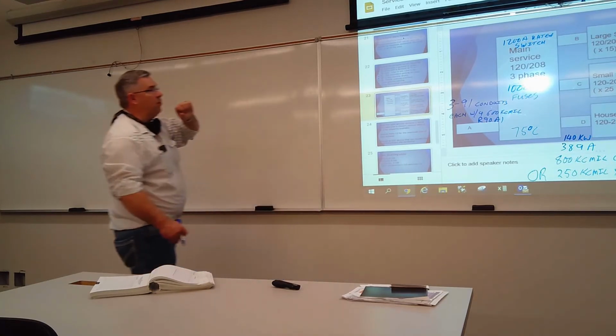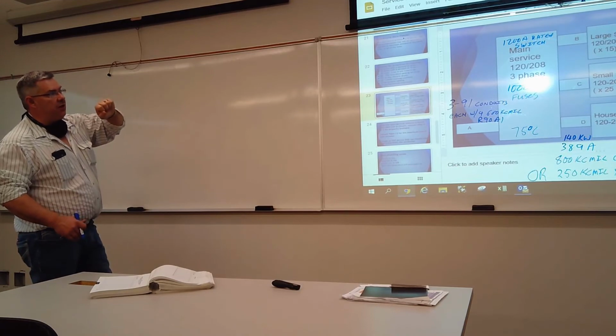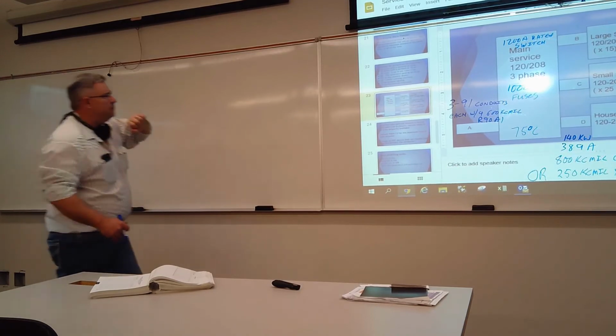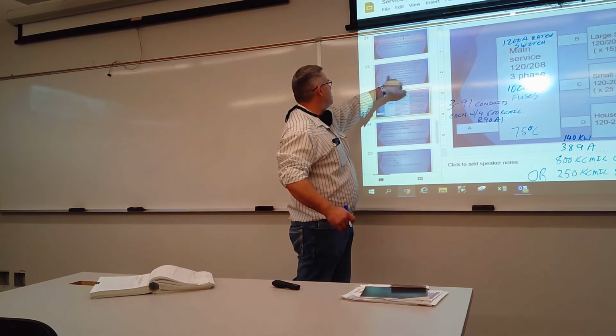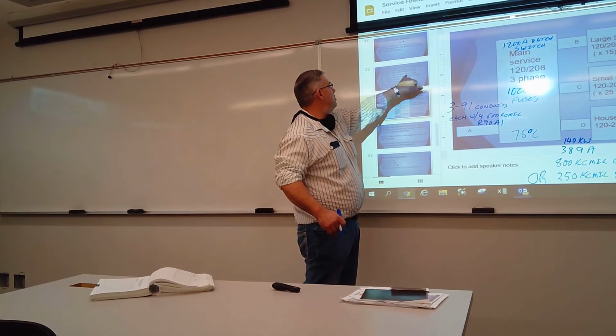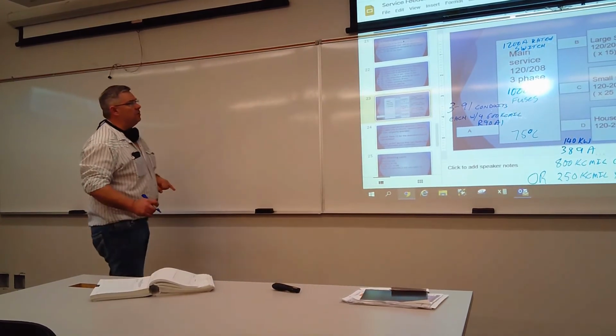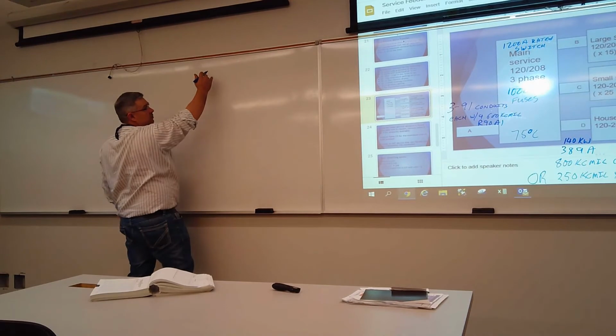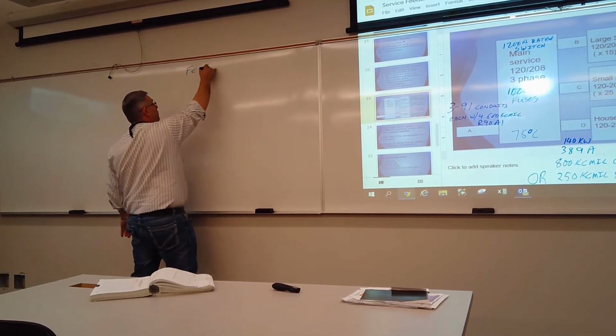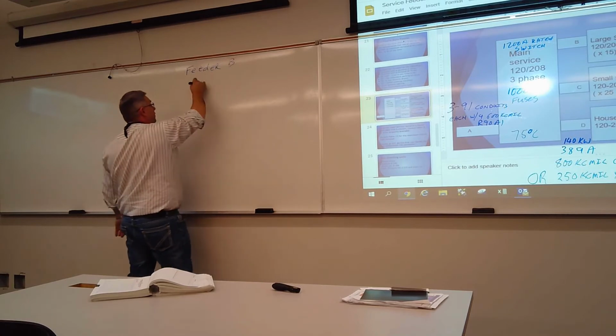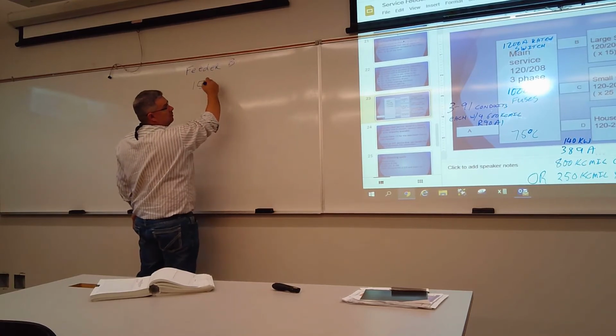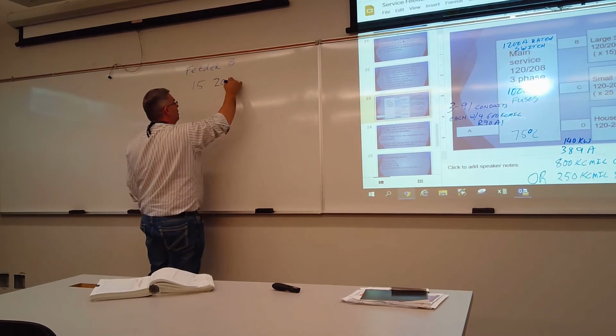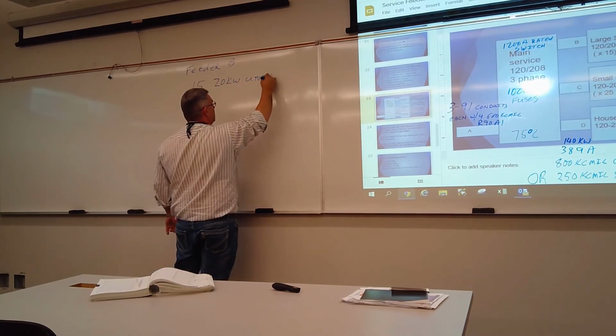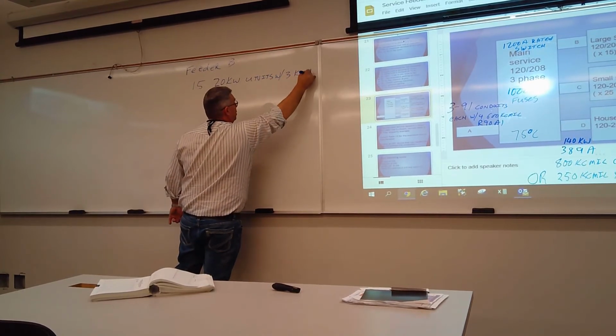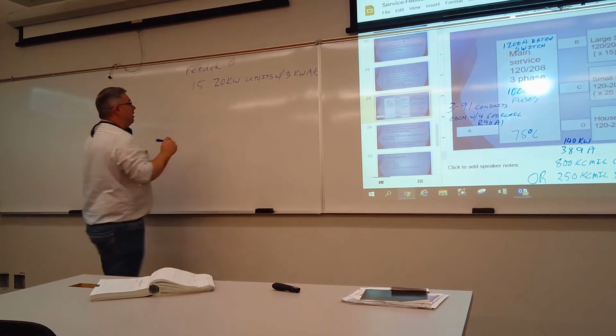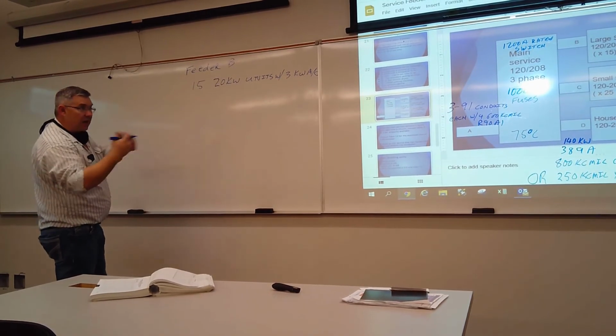Okay, so if all those large suites are fed out of one conduit, they were 20 kilowatt suites with 3 kilowatt air conditioners. So there was 15. Let's call it feeder B, 15 units of 20 kilowatts with 3 kilowatt AC units in them. So again, we have to take the AC out.